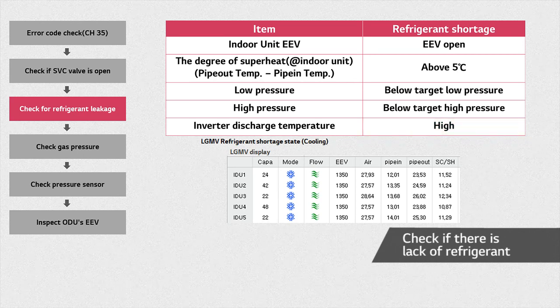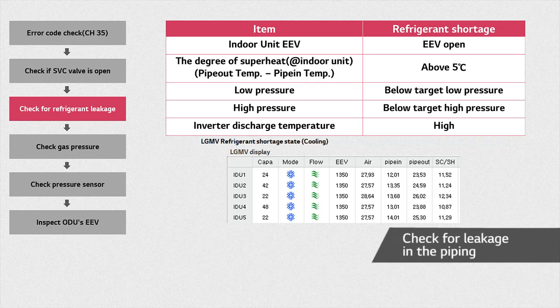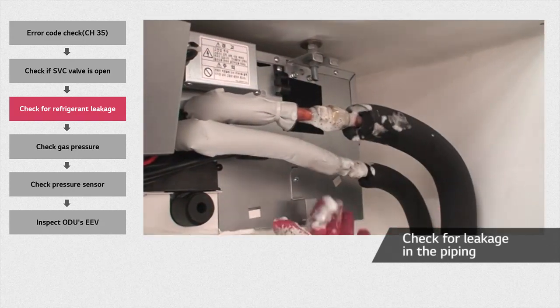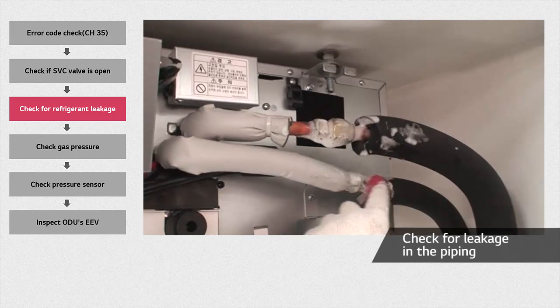Low refrigerant volume may cause excessive discharge temperature. There are two possible causes for lack of refrigerant: maybe the right amount was not charged into the system from the very beginning, or there is a leakage in the piping. Check the brazing and flare connections of the air conditioner. To make sure there are no refrigerant leaks, check for bubbles. Also, check that the piping is not deformed.